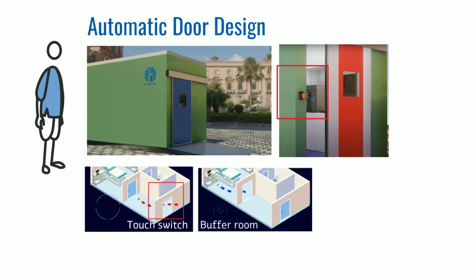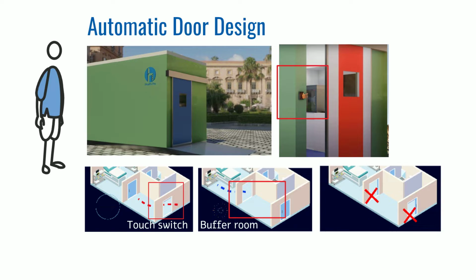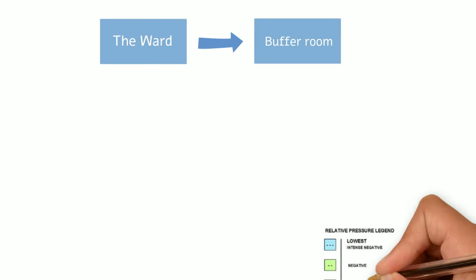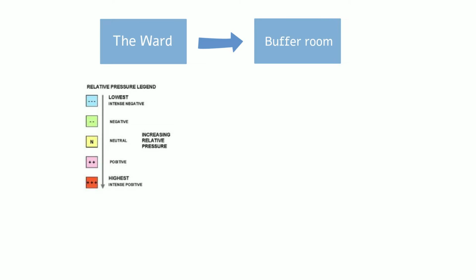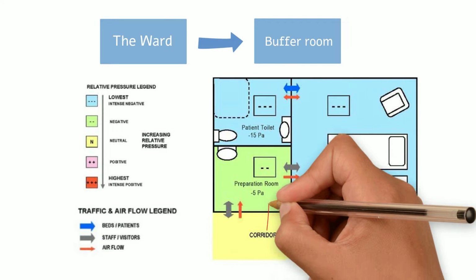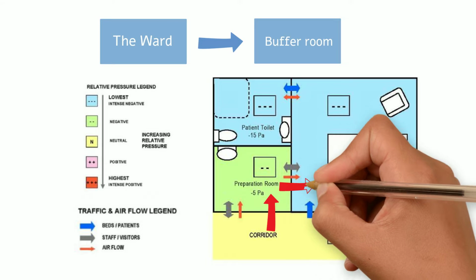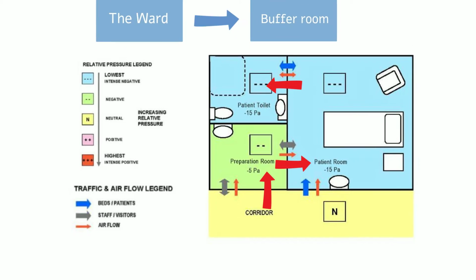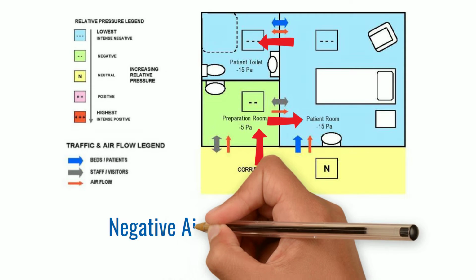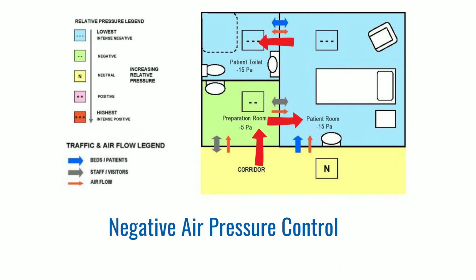Then we will enter a buffer room which maintains negative air pressure relative to the outside space. After walking into the buffer room, we have to wait until the first door closes before opening the second door. In addition, the system will automatically adjust the air pressure between the ward and the buffer room. The air pressure in the ward is lower than that in the buffer room, and the air pressure in the buffer room is lower than that at the outdoor. As the air flows from high pressure area to low pressure area, it can control the air to flow into the ward in one way. That is to say, every time the door is opened, there will be negative air pressure control in order to ensure the air will not leak and maintain the room in negative air pressure.